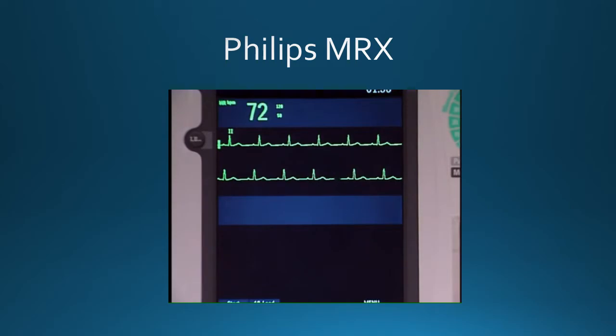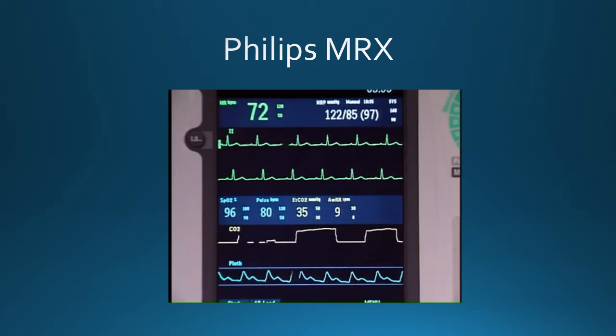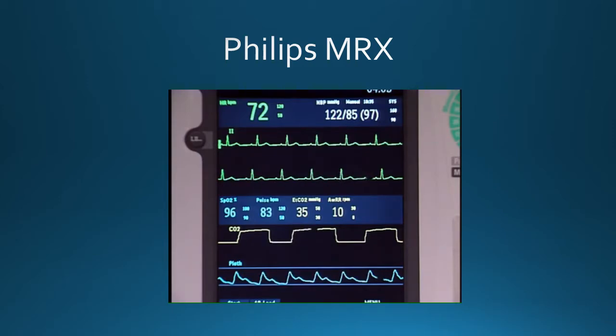The MRX is configured to populate each wave sector with a predetermined waveform. Wave sector 1 will only contain an ECG waveform, which is used by the arrhythmia, heart rate derivation, and AED analysis algorithms. If the configured source is not connected to the device when turned on, the first valid ECG source is displayed in wave sector 1. Wave sectors 2 through 4 are automatically populated when parameter cables or tubing are connected. If you connect a parameter source that's not configured to be displayed, it appears in the first empty wave sector.